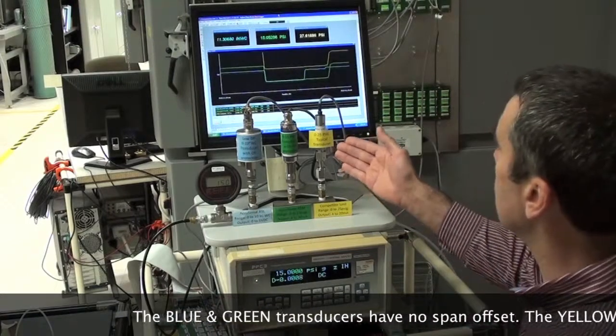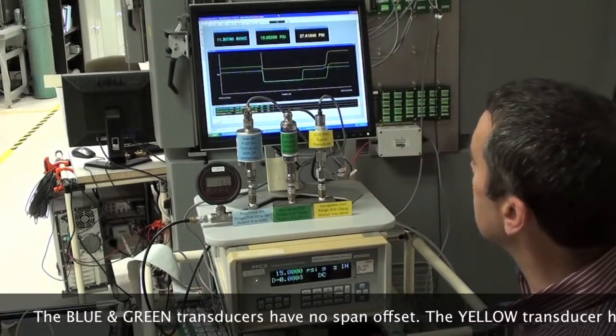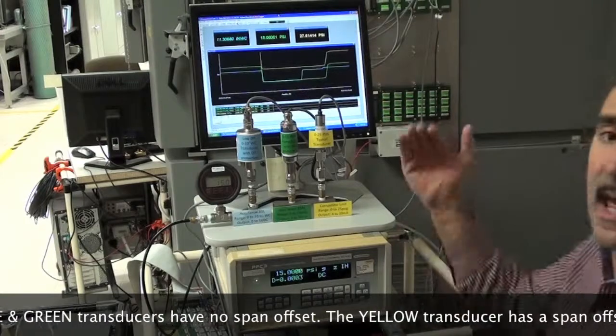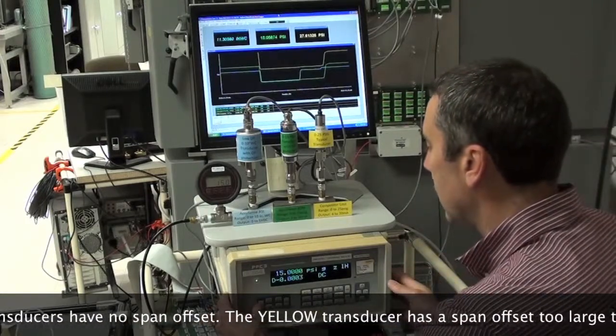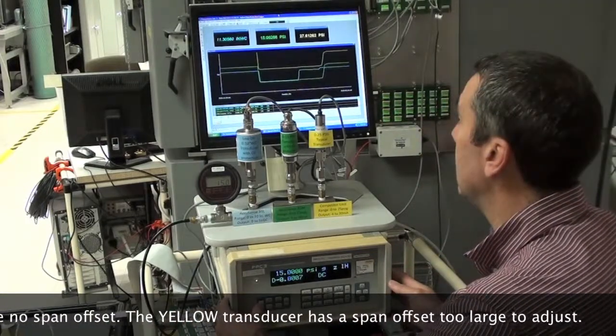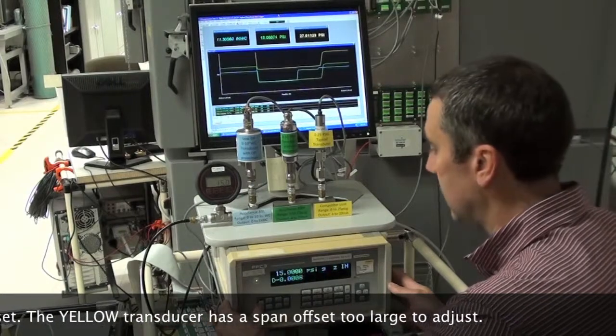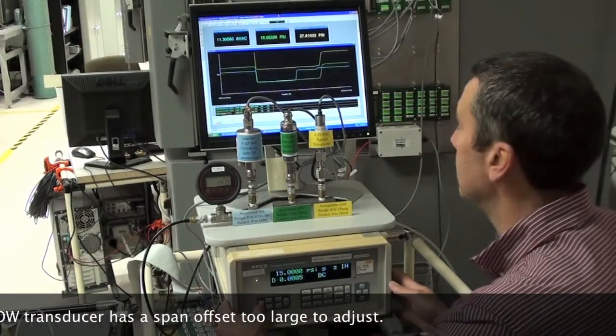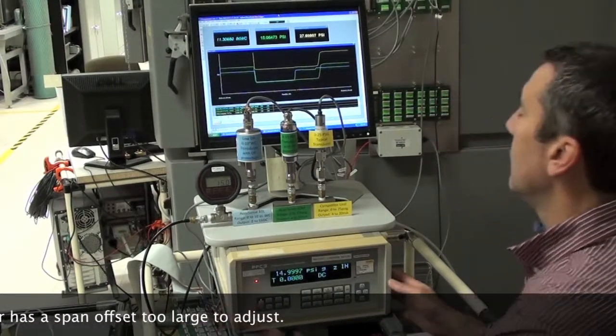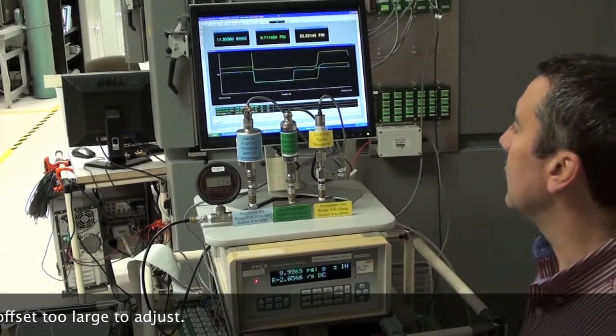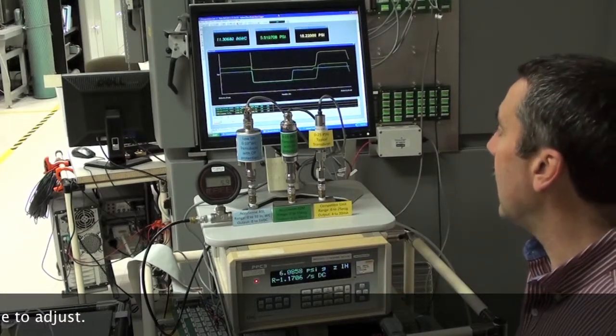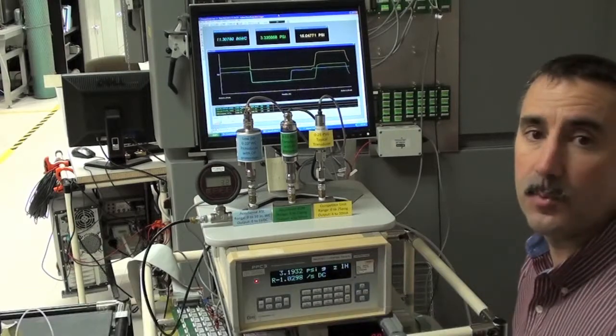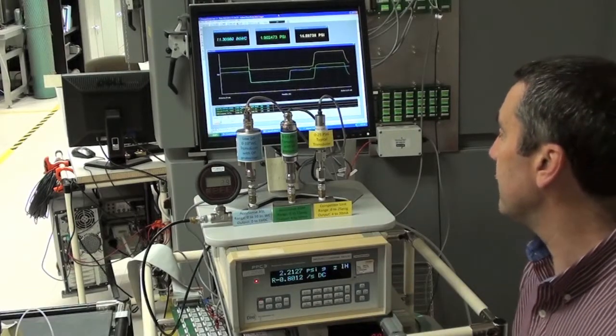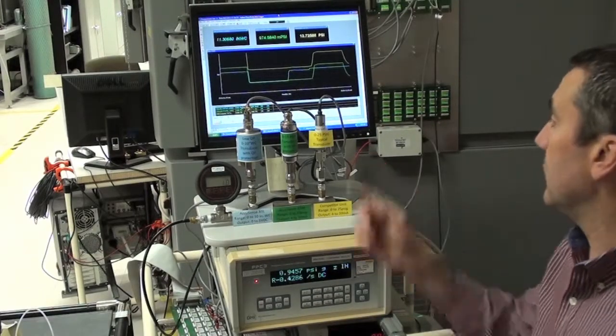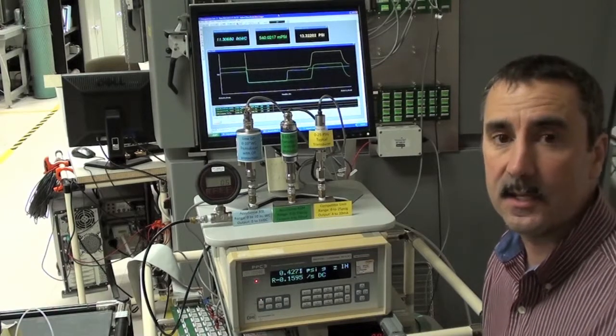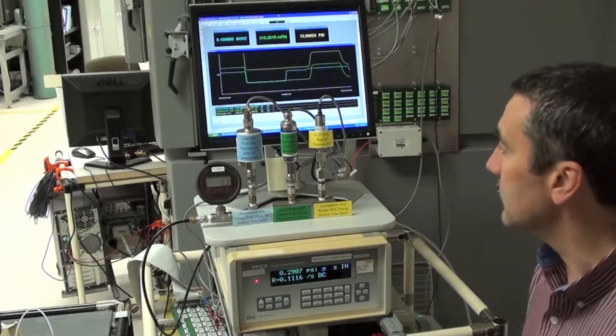So this transducer also was not affected by the overpressure event. The typical transducer, you can see 27 psi. It actually climbed up some more. So it had been affected, and it continues to be affected when you apply the same overpressure to it, which an overpressure event like that pretty much rendered it useless. We will not be able to recover the calibration on this device. There's not enough adjustment on the 0 and span settings to do so, so it's rendered useless.